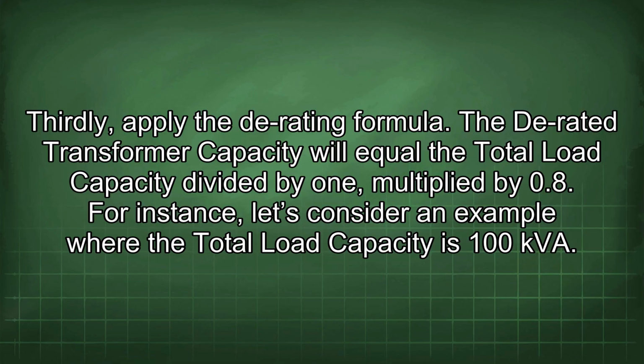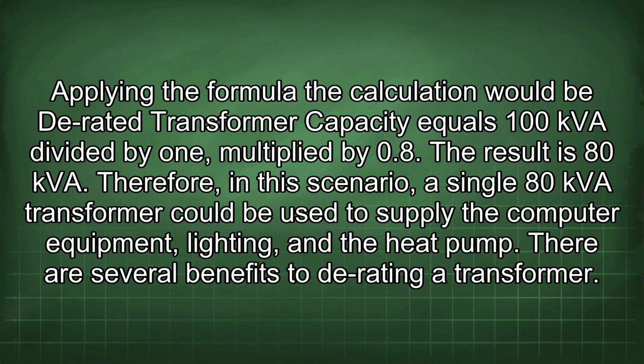For instance, let's consider an example where the total load capacity is 100 kVA. Applying the formula, the calculation would be derated transformer capacity equals 100 kVA divided by 1 multiplied by 0.8. The result is 80 kVA. Therefore, in this scenario, a single 80 kVA transformer could be used to supply the computer equipment, lighting, and the heat pump.